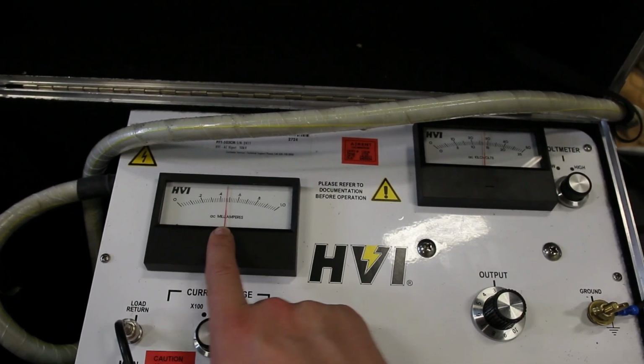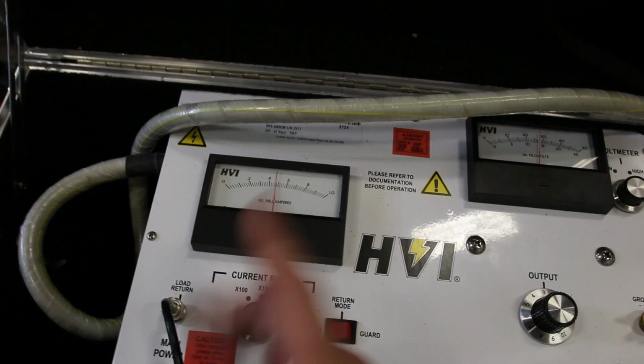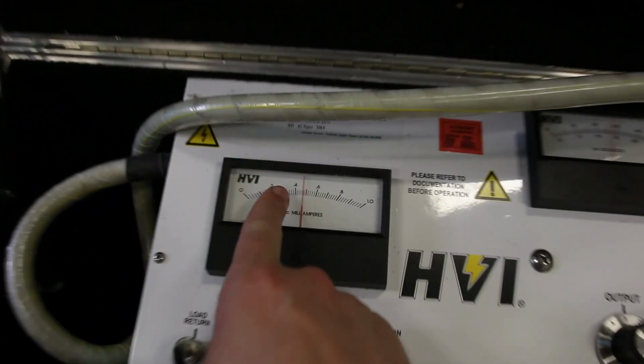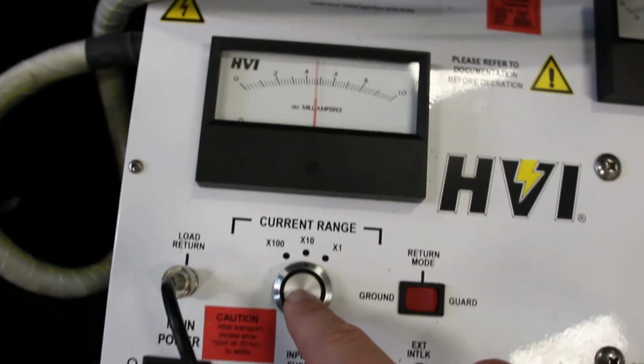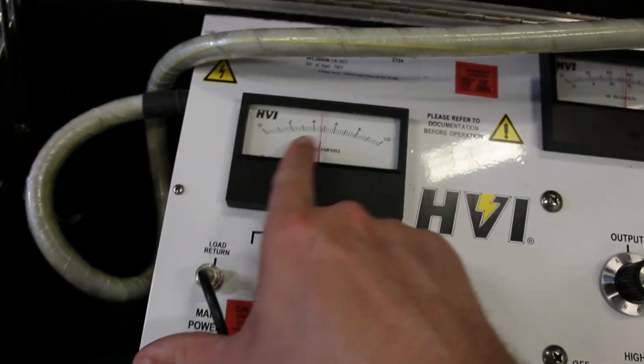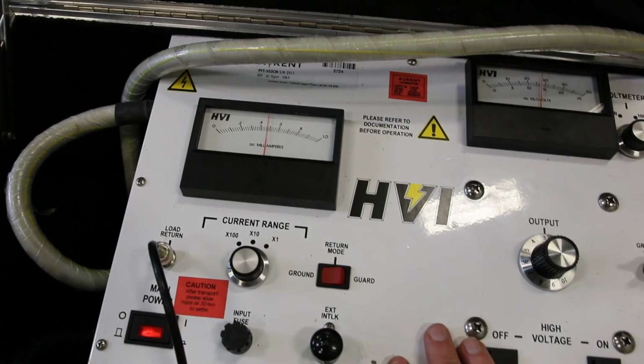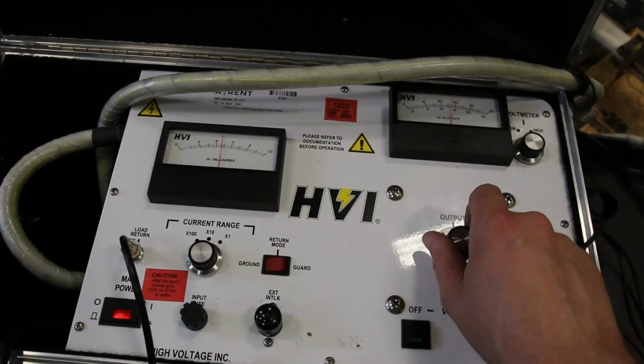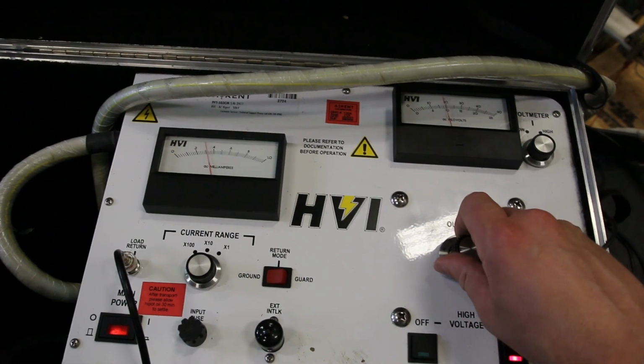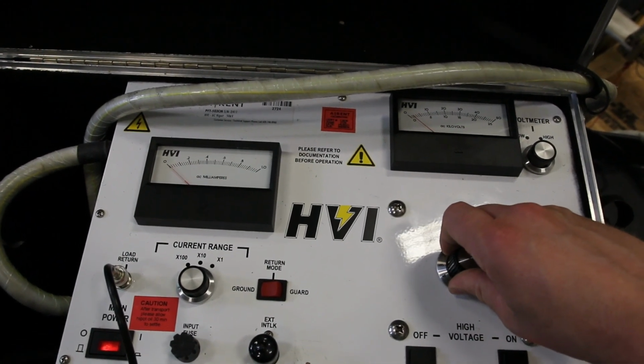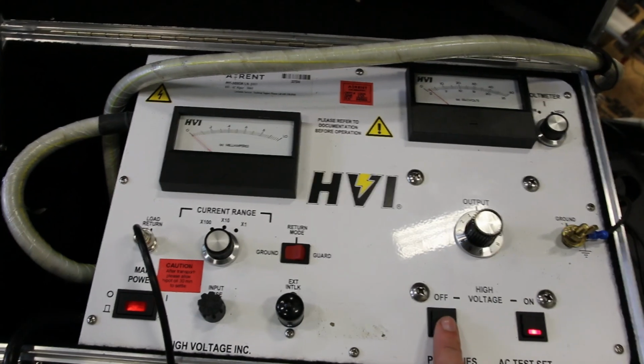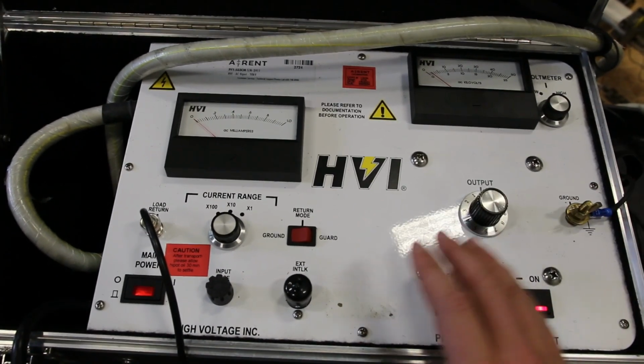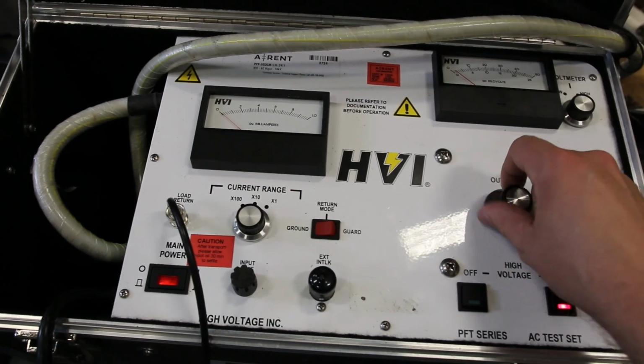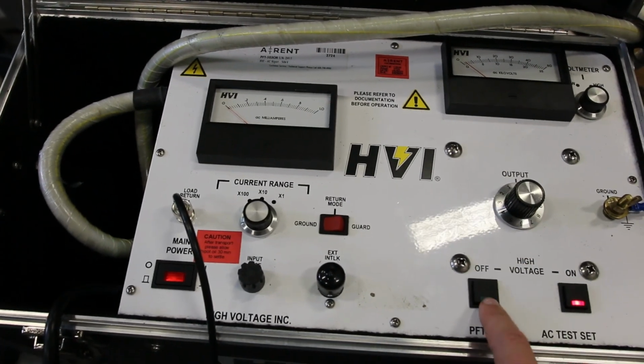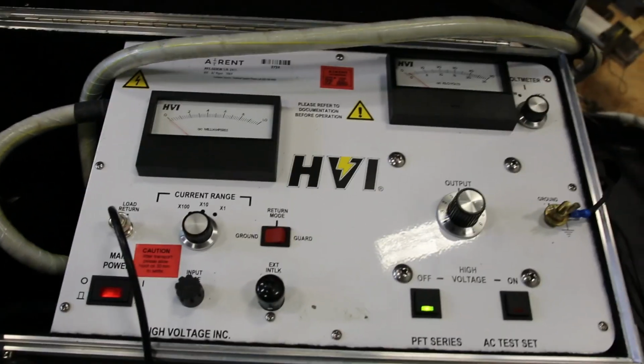And we're chilling at probably about 4.8 milliamps. We're at 0.4 on the scale times 10 on our range selector. So that's 4.8-ish, right under 5 milliamps. So we'll gradually bring that down. I like to slowly turn it off. You can just hit the off button and it grounds the output internally, but you start damaging the contacts inside the high pot. So I like to gradually bring the voltage down. Hit the off button, it grounds out, and we'll do the same on the next phases.